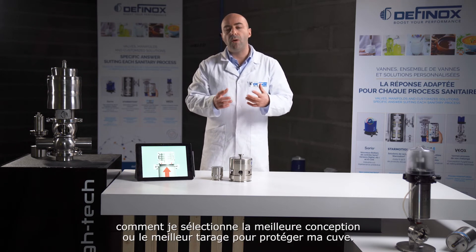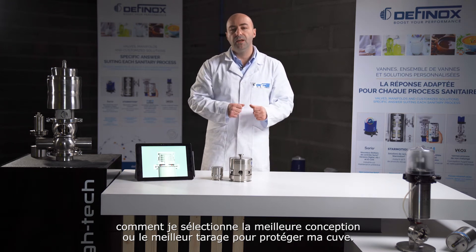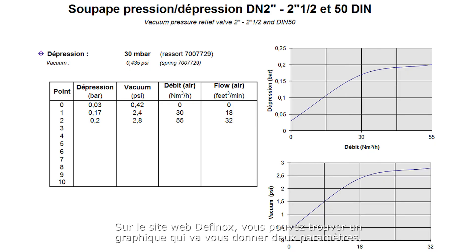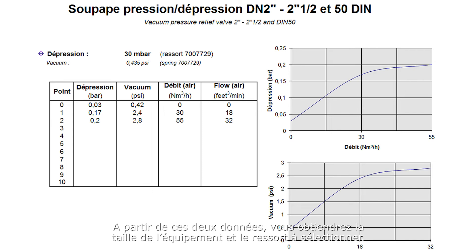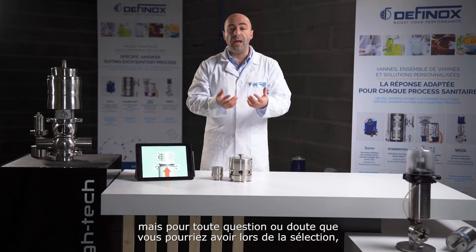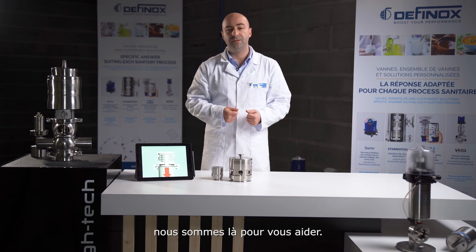The question at this stage is: how do I select the best design or preset to protect my tank? On the Definox website you will find a chart that gives you two parameters — the flow to exhaust and the maximum pressure you would like to reach in your tank. Based on these two data points, it will give you the housing size and the spring to select. For any question about the selection process, we are here to assist you.